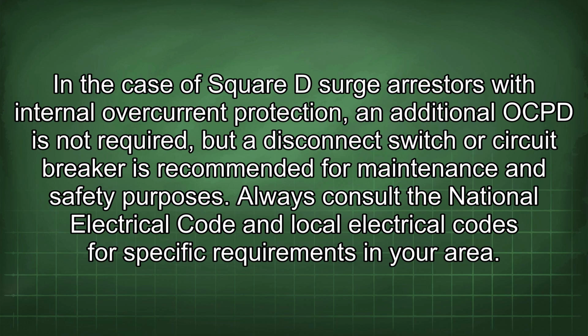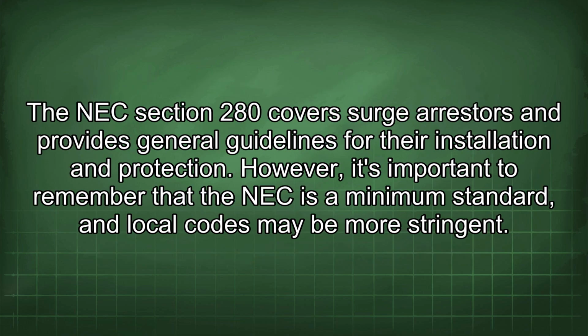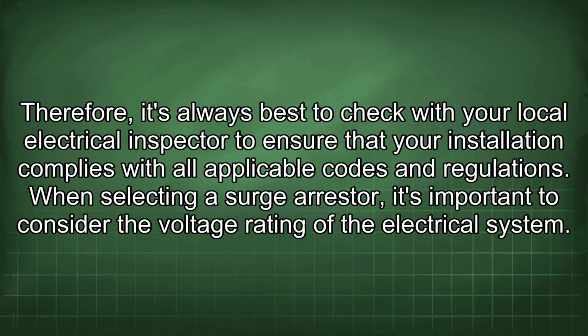Always consult the National Electrical Code and local electrical codes for specific requirements in your area. The NEC Section 280 covers surge arrestors and provides general guidelines for their installation and protection. However, it's important to remember that the NEC is a minimum standard, and local codes may be more stringent.